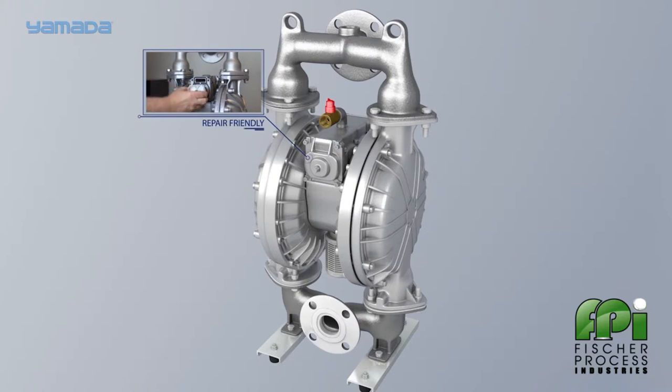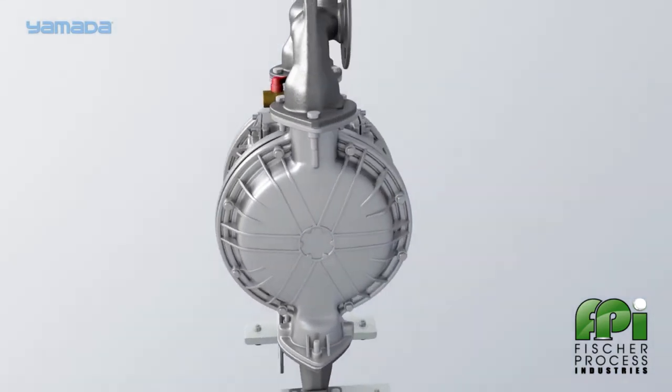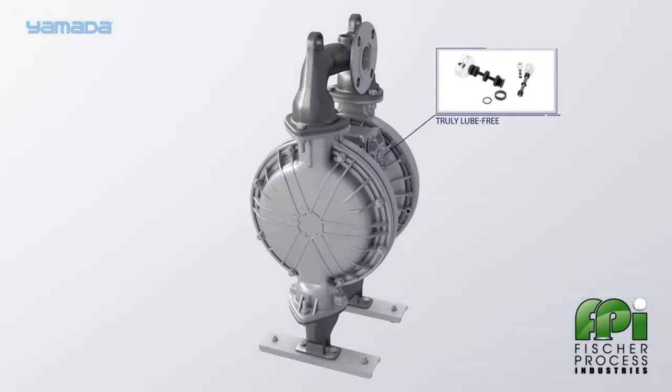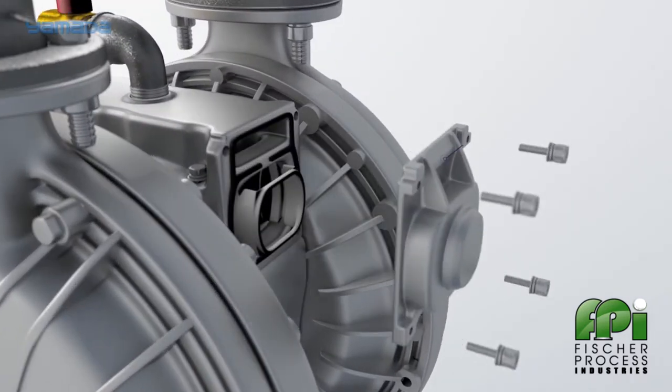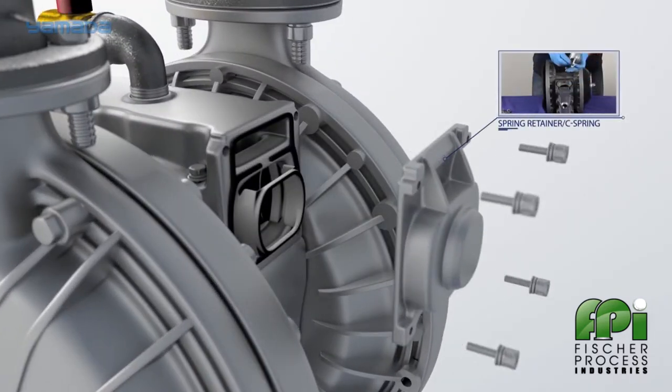Yamada air valves have the longest service life in the industry due to its lube-free design. The non-lubrication design is important because one of two things can happen when lubrication is needed: one, lubrication can be washed away by the moisture in the air causing wearing issues, and two, moisture and particulate can coagulate and create a sandpaper effect, hence causing more wearing issues. Each air valve also contains a c-spring, helping to ensure a positive shift every time.